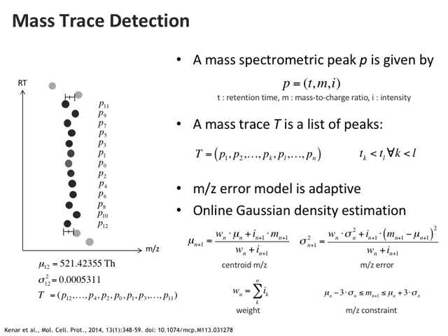Yes and no. So what you describe is something that happens and has happened to us in TOF data quite a bit, because you can have saturation effects that change the shape of the peak. Note that these are mass spec peaks, not chromatographic peaks. So we call that the banana effect, because what happened is that the saturation shifted the masses in the high intensity range to the right.